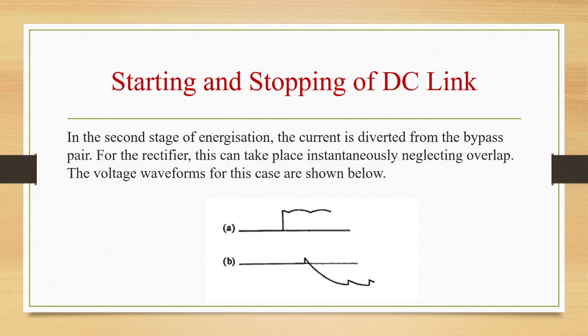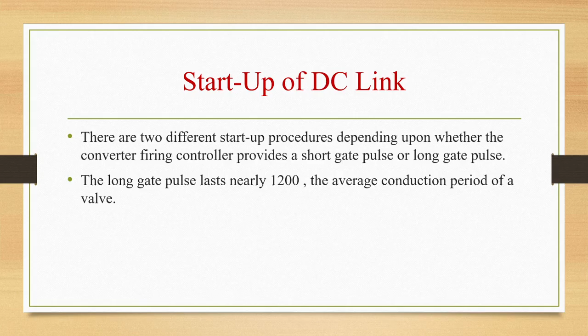So here we can note a point that to avoid operation at high delay or extinction angles, the de-energization of a bridge at the rectifier or inverter station is accompanied by the de-energization of a bridge at the inverter or rectifier station. Let us see startup of a DC link. There are two different startup procedures depending upon whether the converter firing controller provides a short gate pulse or a long gate pulse. The long gate pulse will last nearly 120 degrees, the average conduction period of a valve.